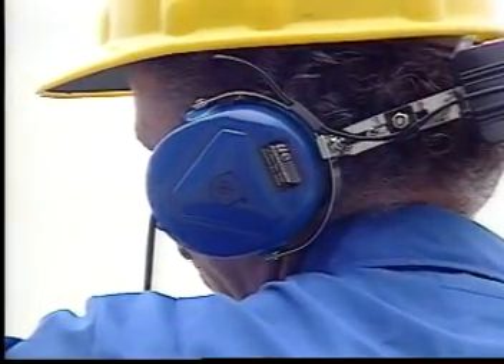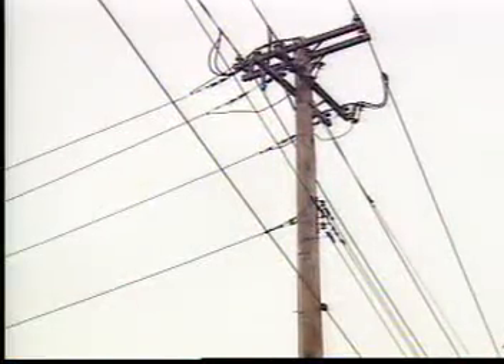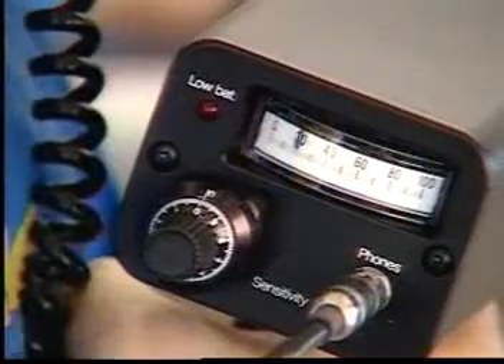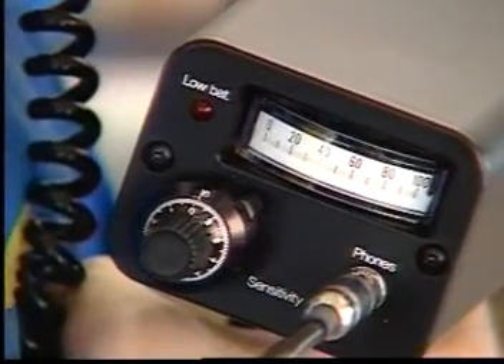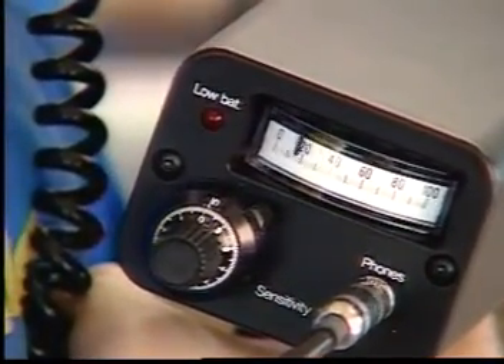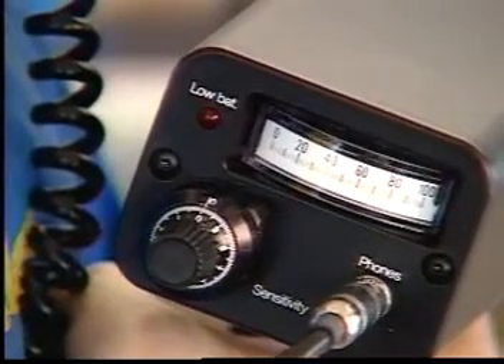With experience, you learn to detect changes, know when further investigation is required, and recognize a gradually worsening condition. However, you won't hear any real indicators relative to time for destructive corona. The time to correct the problem is immediately. An explosion may happen sooner or it may happen later, but it can happen at any time and without warning. This is the actual sound of destructive high-voltage corona at a severe stage.